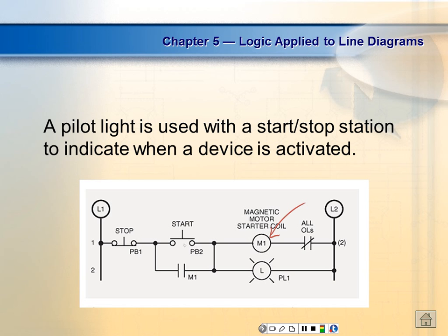Well, I don't know what you mean. I come up here, I hit this button. This is in parallel. So if this one right here is on, this one right here should be on. I come over and press the start button, and that right there closes. Both lights are on. What he's saying is, the light on the start button, as soon as you touch that start button, it's going to instantly come on. Right. M1's bad, as long as you hold the start button. Yeah. Okay, I understand. You're saying if M1 was bad. Yeah. I didn't know you were talking about a problem. Yeah, if M1 is bad, it won't seal in.